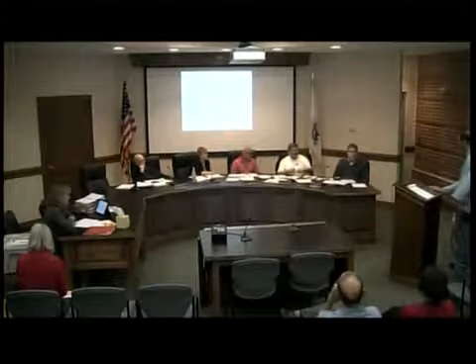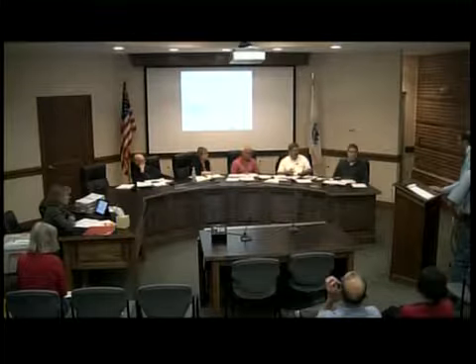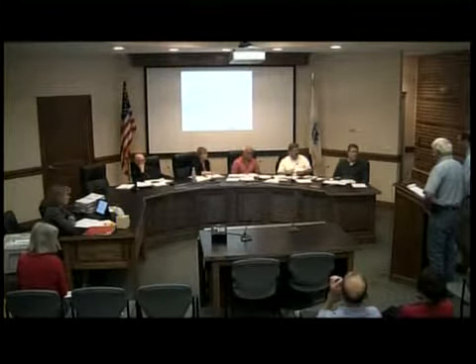And really, the thing that's the most vulnerable is the generator, and it's a temporary location for a skid-mounted generator sitting on stone. I mean, is there any other place? It'll probably be a trailer-mounted unit. Trailer mounted? So it'll be up high. And the pad itself is 2 feet above the flood elevation. Right. Yeah, we've actually had the pad designed higher than the existing pad.